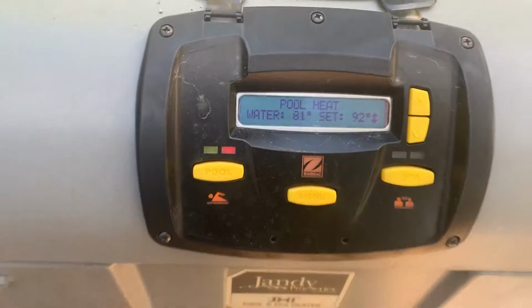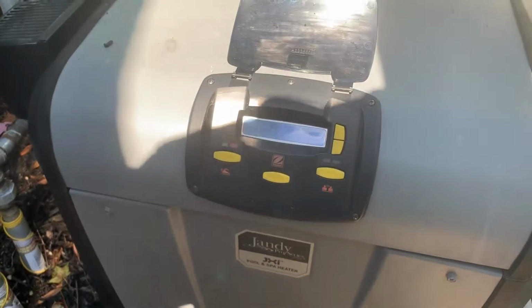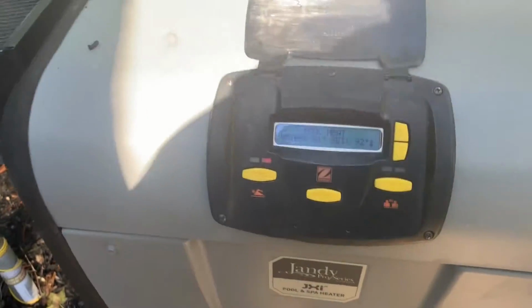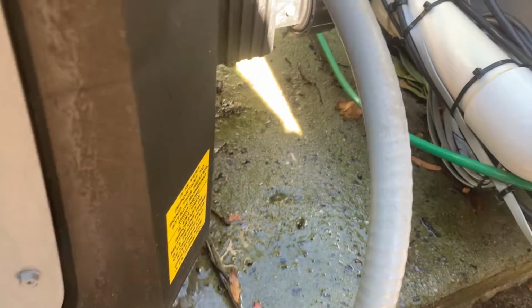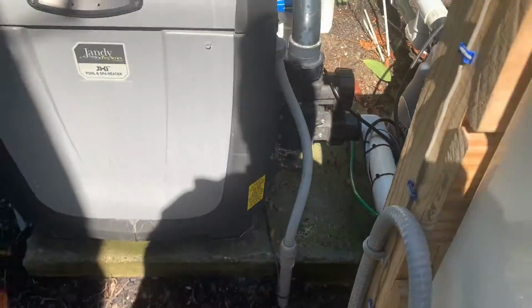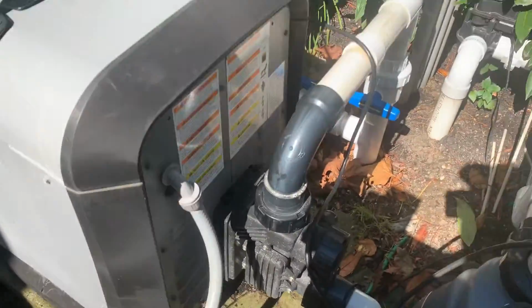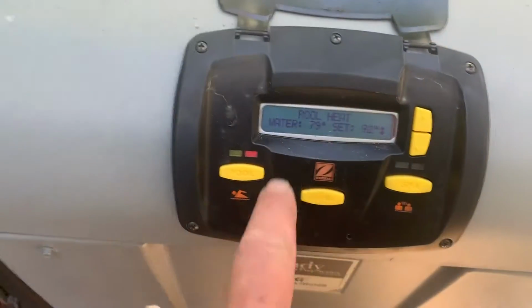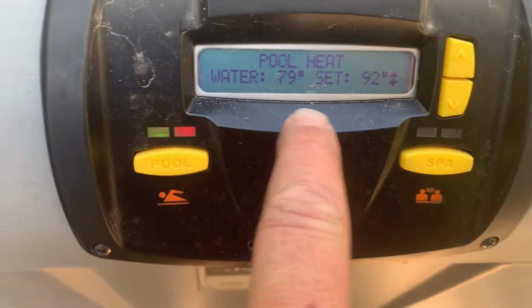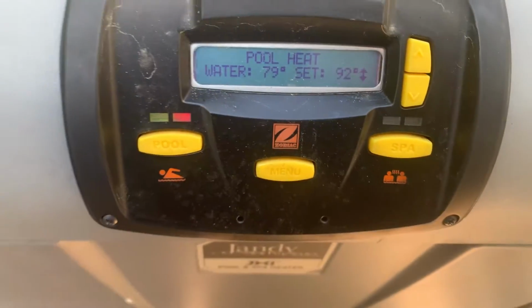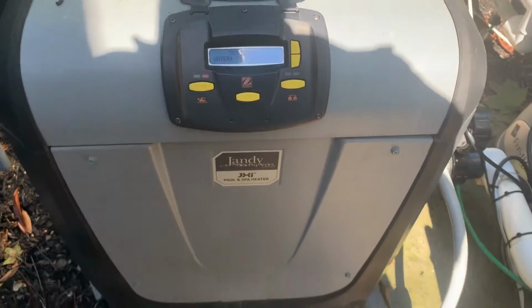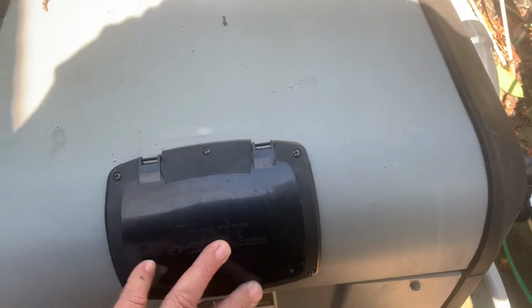He had an error of high flue temperature. One of the things you notice, when I first got here, I see some water around the base of the pool heater. It's dripping. I just turned it on, and water temperature is 79 degrees. It's set for 92, and I hear some gurgling in there. Something's not right. So I already know what's wrong.